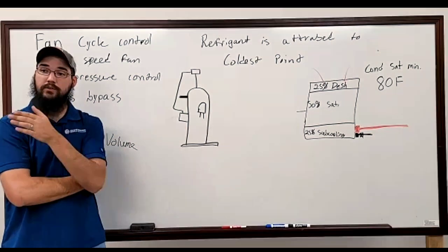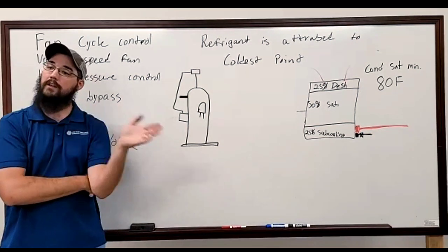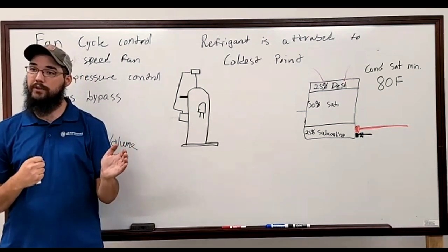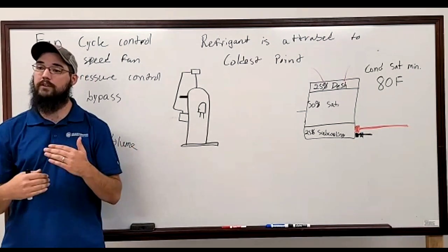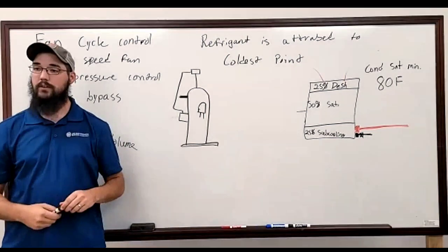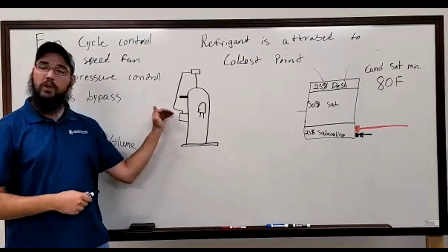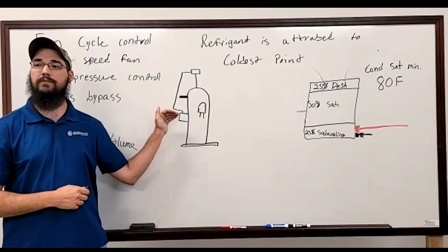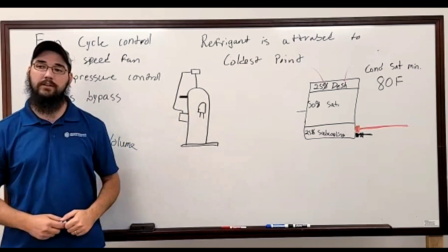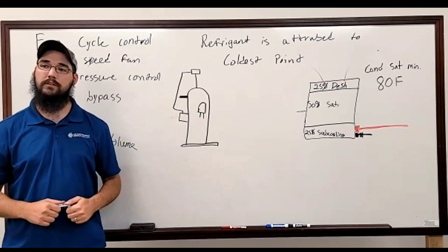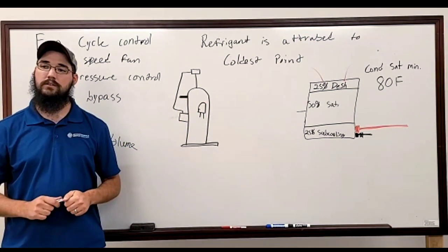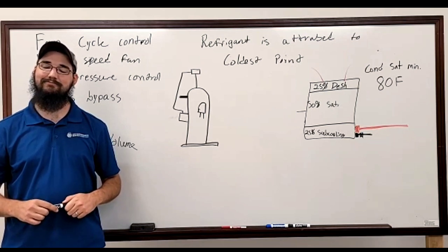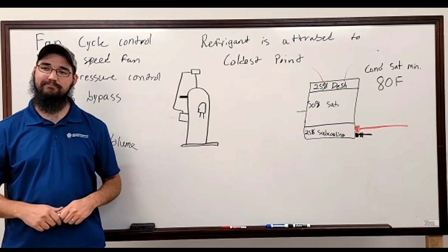Right? Yes. Right. Yeah, and so because your amps are lower, your kW is lower, which means the heat you're introducing to the refrigerant, the additional superheat, is reduced. And even though you're flowing a lesser amount through the suction line, what you are flowing is still enough to handle the heat load being generated. So you don't end up with the heat. Yeah, I was just wondering, like, push the hot gas to the discharge. To me, it seems like it should come back super, super hot into the suction, but I guess the suction's cooling it off.